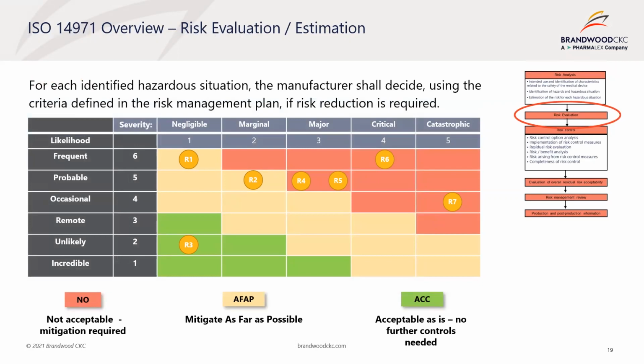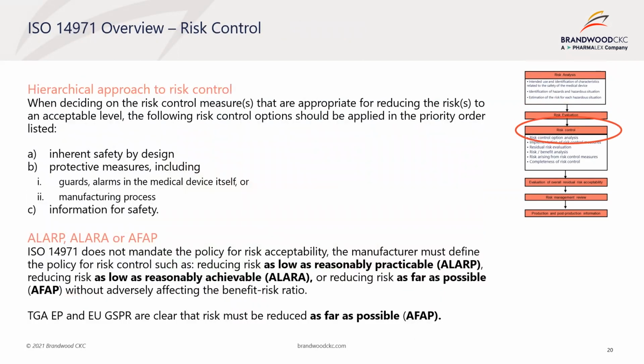It is important to point out that the expectation of regulators is that all risks are individually addressed. The matrix presented may be best to understand the suitability of risks, but each risk needs to be individually addressed. Several options exist to reduce risks associated with medical device. This can be used alone or in combination. The manufacturer can explore different options to reduce the risk to acceptable levels. The order of priority is important here.